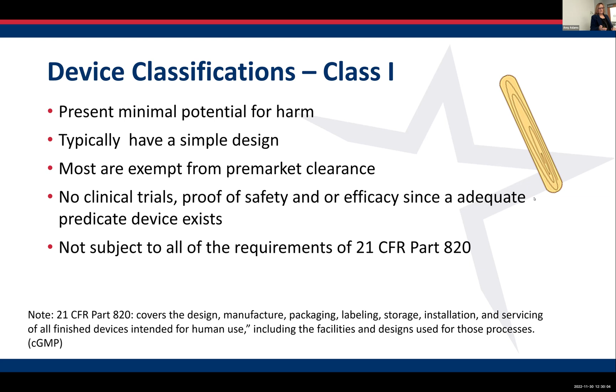Okay, so that's class 1. So what are the requirements? You have to register with the FDA. The device has to go on the register. It's a medical device listing. You have general FDA labeling requirements. Labeling is super, super important, and I have an example story. If we have time, I'll tell you about one of my experiences with labeling. And you have to have compliance with a quality system. So that's another reason why I'm really strong early on. The earlier you start building your quality management system, the better off you are. So examples are bandages, exam gloves, tongue depressors, surgical masks, stethoscopes. So simple things that you see every day.